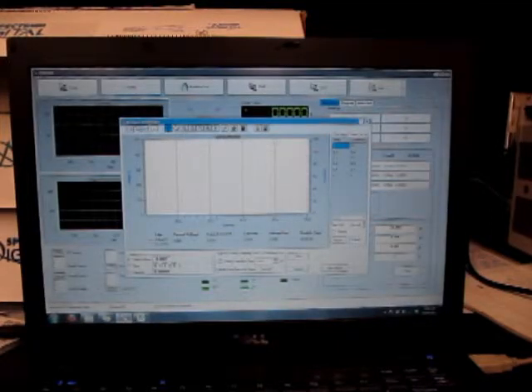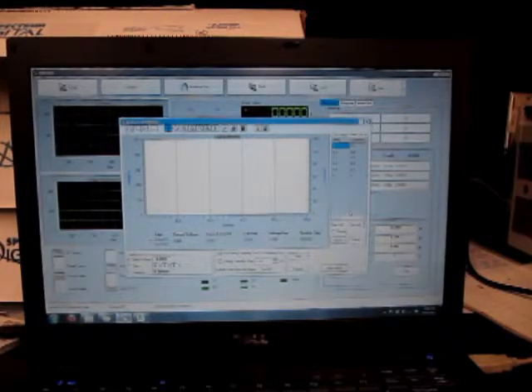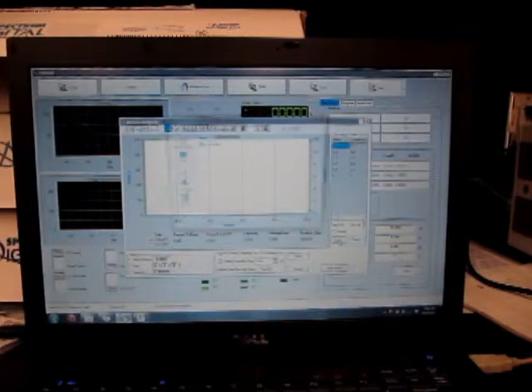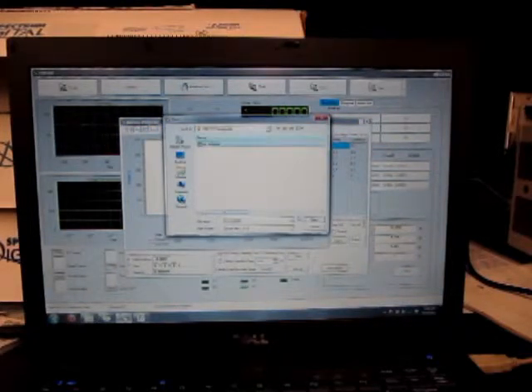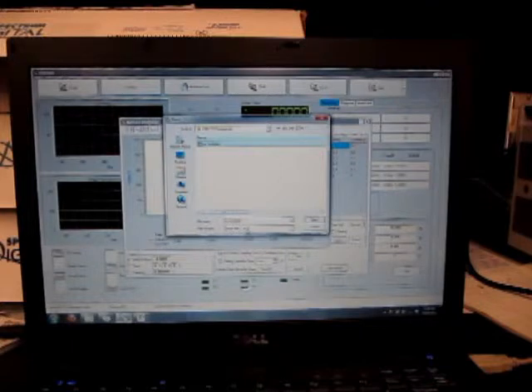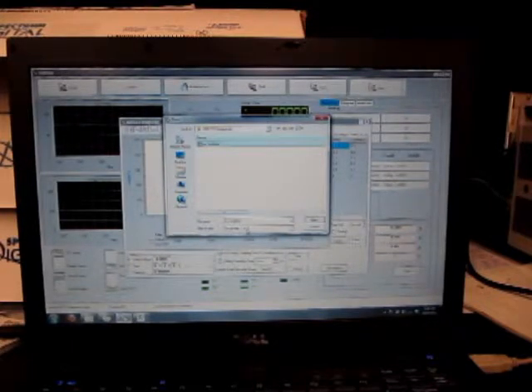And then go back to the battery discharge and click on import. And I want PV test plan. Notice this is a XLS. So you need to make it 2003 compatible when you save it in Excel 2010 or 2007. So let's open that up.